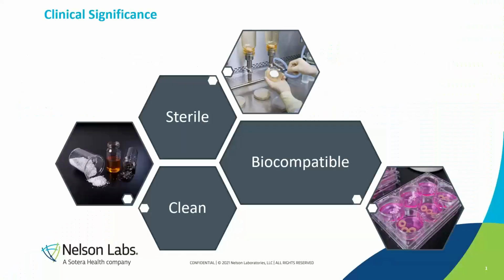When evaluating medical devices for safety purposes, I think many of us are pretty familiar with sterility and biocompatibility programs, at least as far as the necessity of each and the regulatory expectation for a successful assessment. But there is still often confusion on the role and the value of a cleanliness assessment. Because if it passes current biocompatibility requirements, then the device is clean enough.